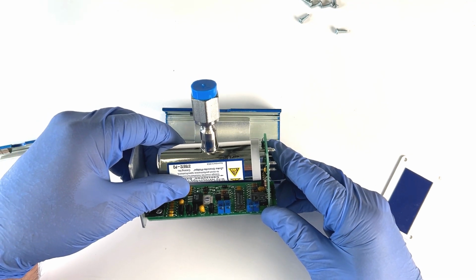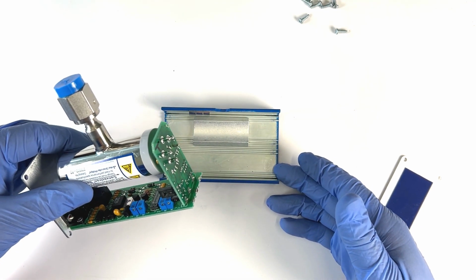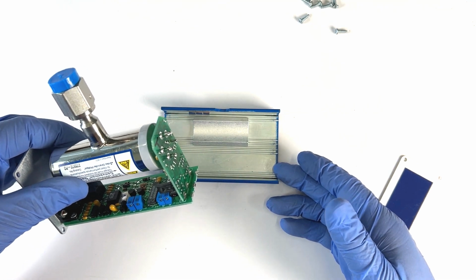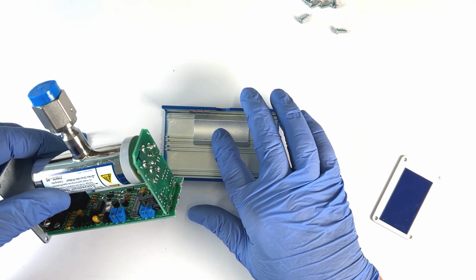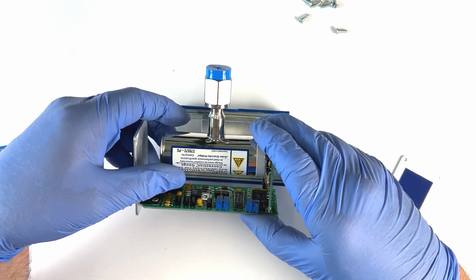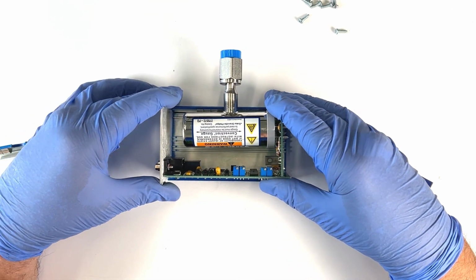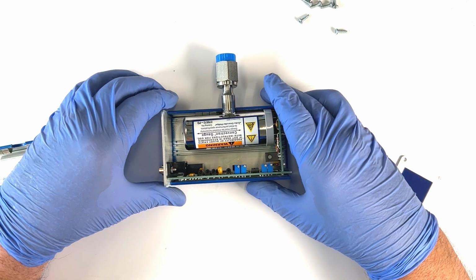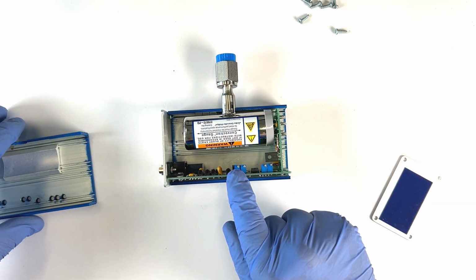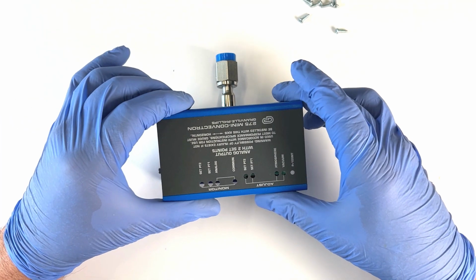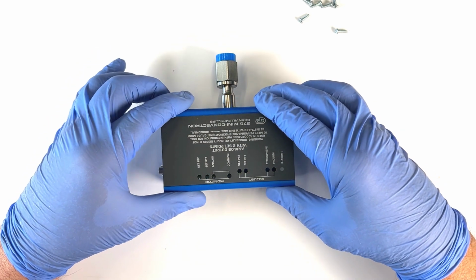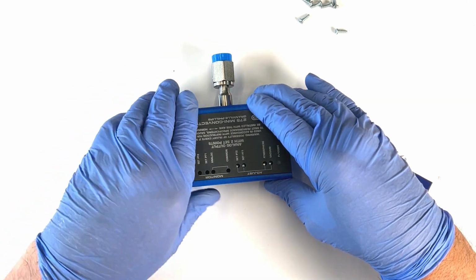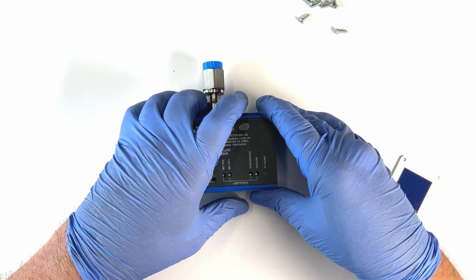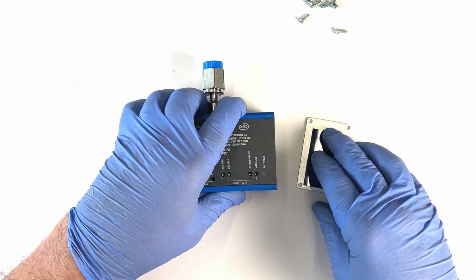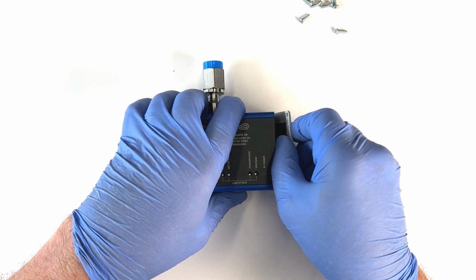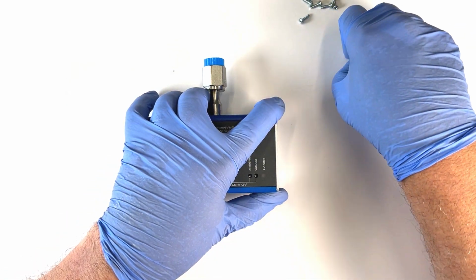Position the internal assembly into one side of the blue housing, making sure the gauge grounding springs and cradles are in line with the gauge envelope, and that the set point screws are on the side of the housing with the access holes. Reattach the end plates with the Phillips head screws.